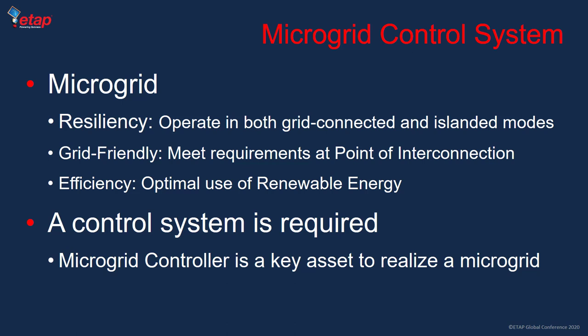Another key attribute of the microgrid is that it makes combinations of distributed energy resources and loads more grid-friendly. There are typically several requirements at the point of interconnection to the main grid, and the microgrid control system meets those requirements. For example, a microgrid may not be permitted to export power to the grid at certain locations, so the controller uses energy storage to absorb excess renewable power. There are also requirements for active and reactive power support during disturbances.